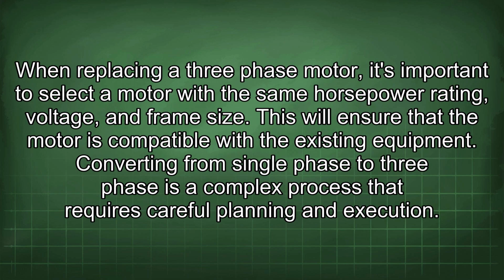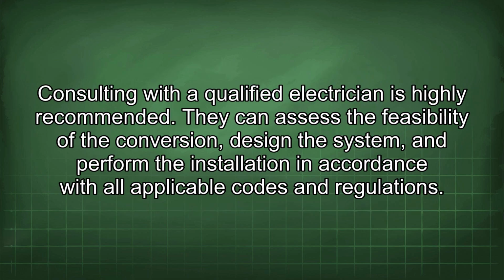When replacing a three-phase motor, it's important to select a motor with the same horsepower rating, voltage, and frame size. This will ensure that the motor is compatible with the existing equipment. Converting from single-phase to three-phase is a complex process that requires careful planning and execution. Consulting with a qualified electrician is highly recommended. They can assess the feasibility of the conversion, design the system, and perform the installation in accordance with all applicable codes and regulations.